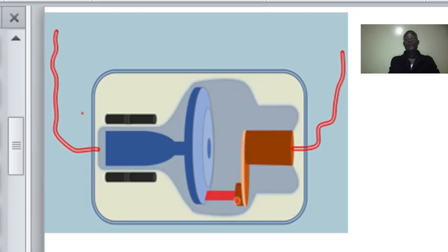Now, normally, as I had said, we use high voltage in X-rays. So in X-ray tubes, we accelerate the electrons. Normally, electrons are produced within the filament, where we have our filament here. Electrons are produced here after a supply of current has been made into it. Then through the thermionic process, we are able to produce the electrons. Now these electrons, if they are not accelerated to the anode target, then their production is equivalently useless.